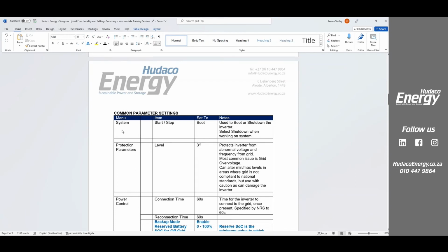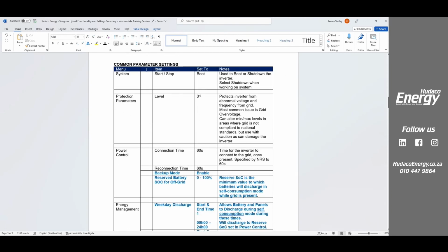Okay, so there's a lot of stuff we're not going to deal with today. We're only going to deal with the stuff that's highlighted in blue, because these are the primary settings which you should go through when you commission the system for the first time for the client. It shouldn't take you much more than 10 minutes to do them all. Okay, so if the wiring is correct, once everything is on the wall and you do it, your commissioning process is 10 minutes. Okay, so start, stop, we put it to boot stage. The other option is shutdown. If you're going to do any work on it, then please go to the shutdown, but normally it must say boot.